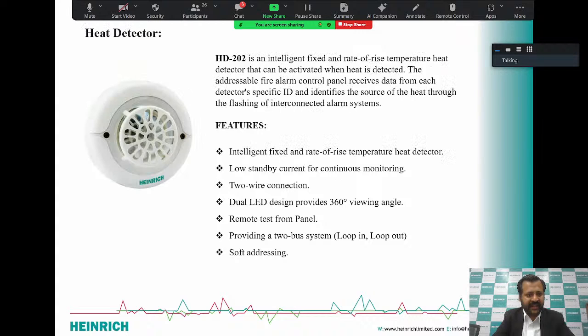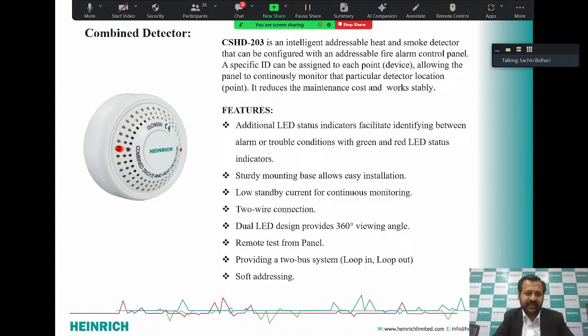Heat detector, again the same way. We have features of it. It is an intelligent fixed and rate of rise temperature heat detector, with low standby current, two-wire connection, and dual LED design providing a 360 viewing angle, remote test from panel, and soft addressing. The combined detector is connected in the same way, and it has soft addressing, two-wire connection, and additional LED status indicators. Again, it has a low standby current for continuous monitoring.